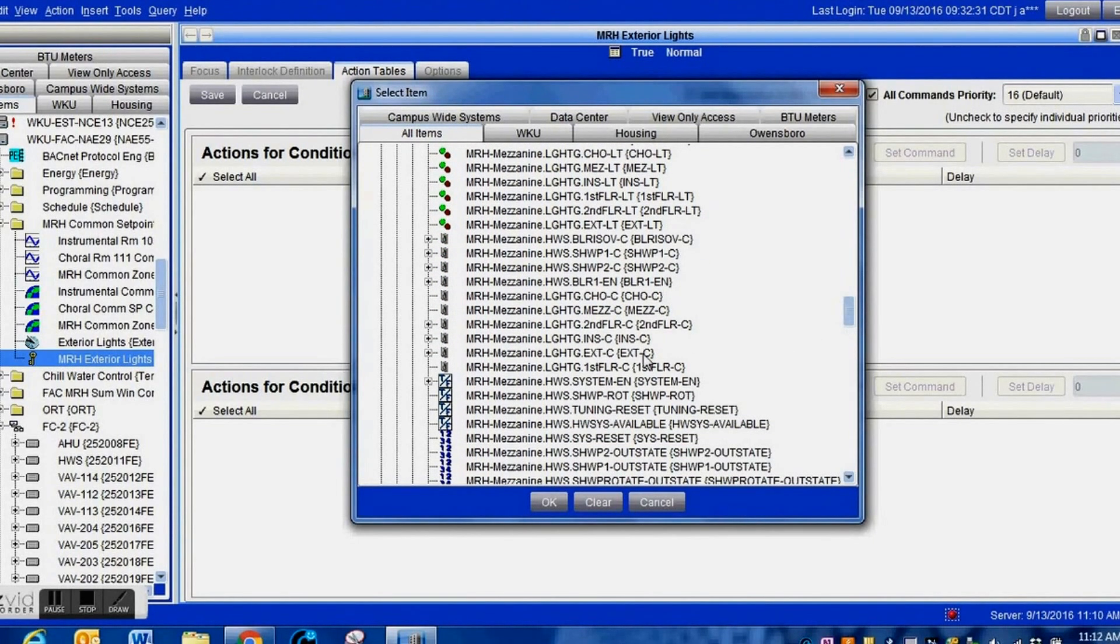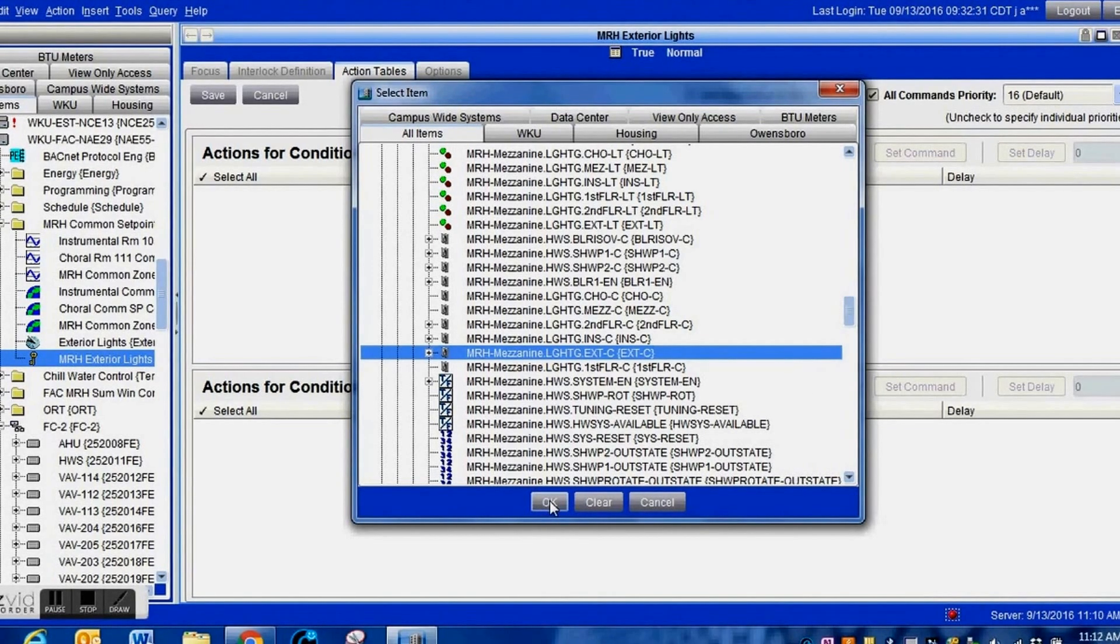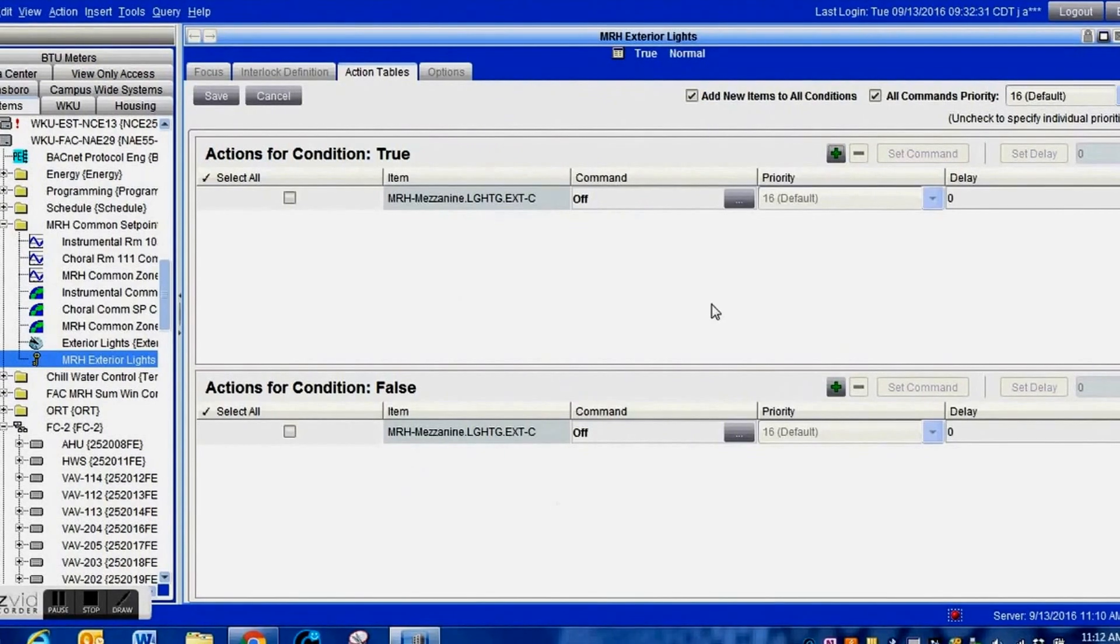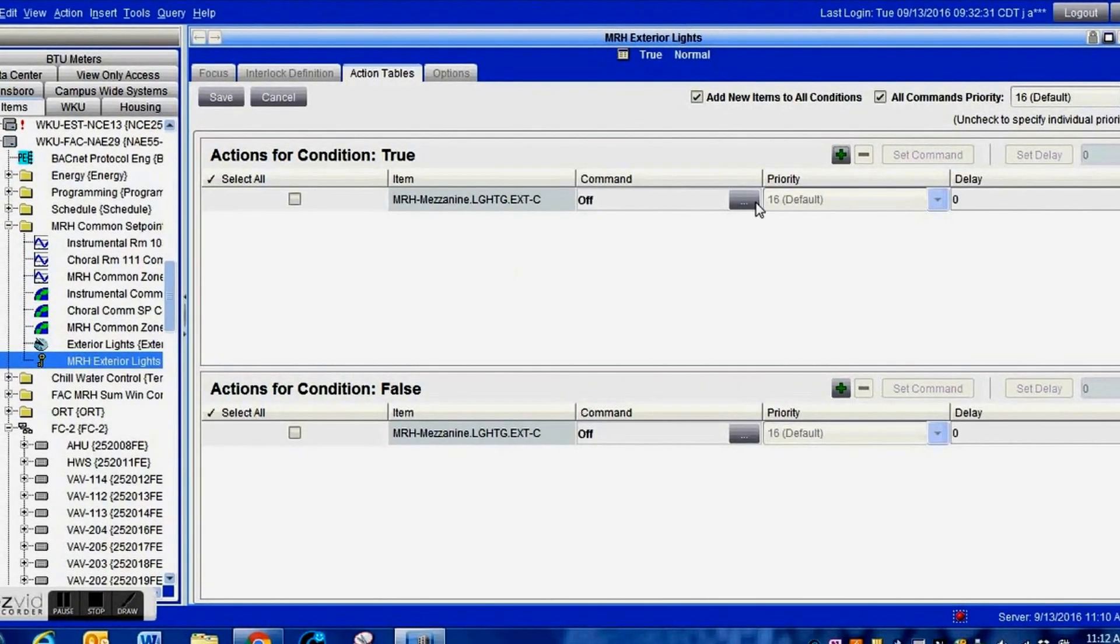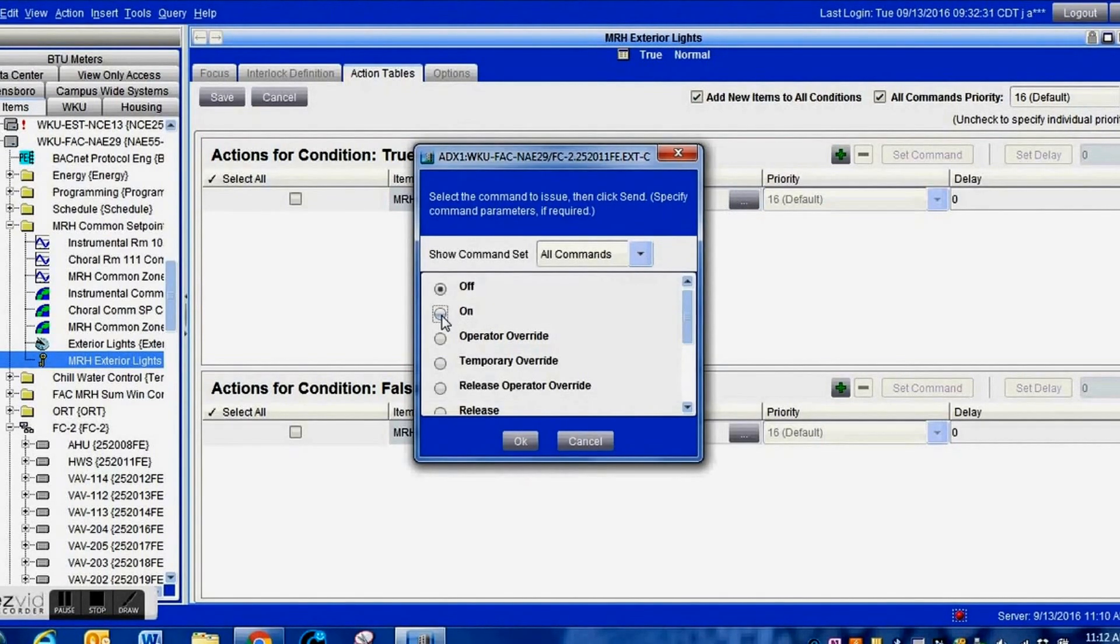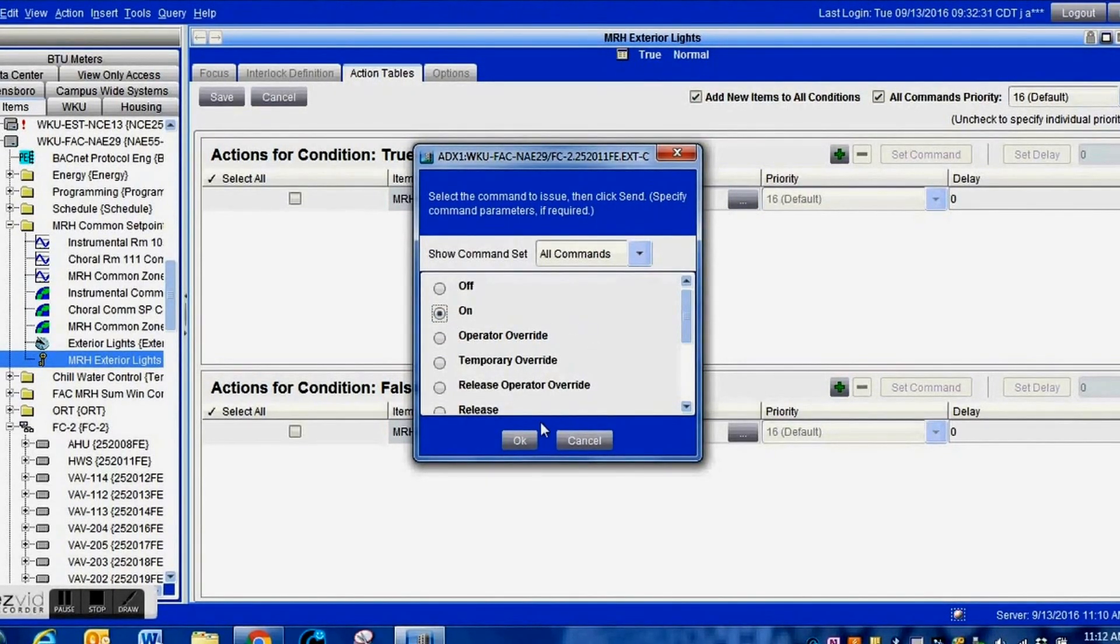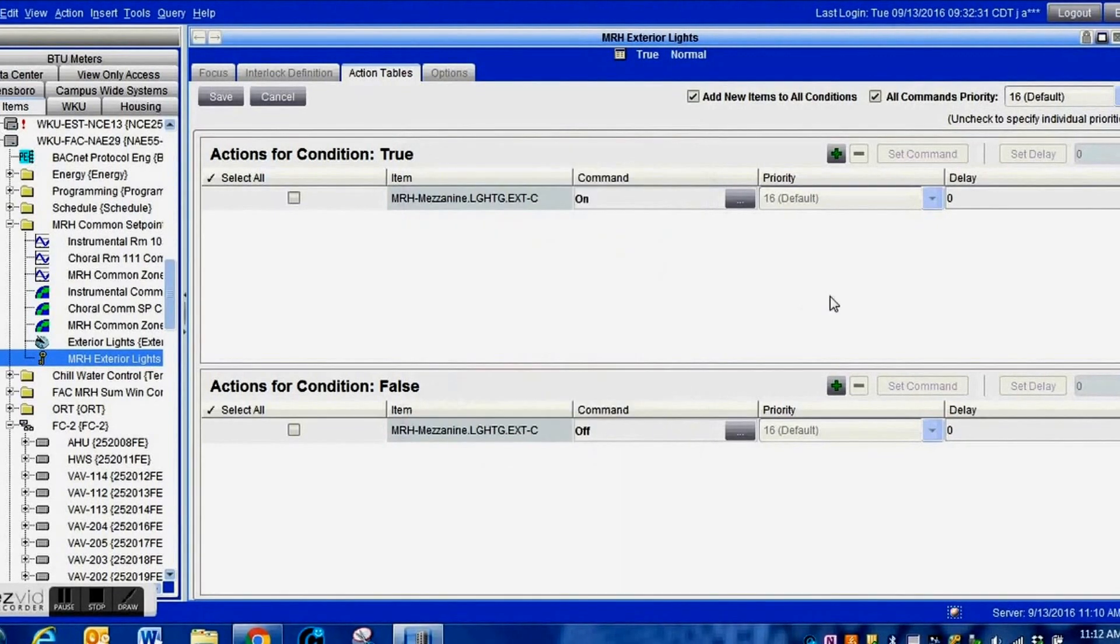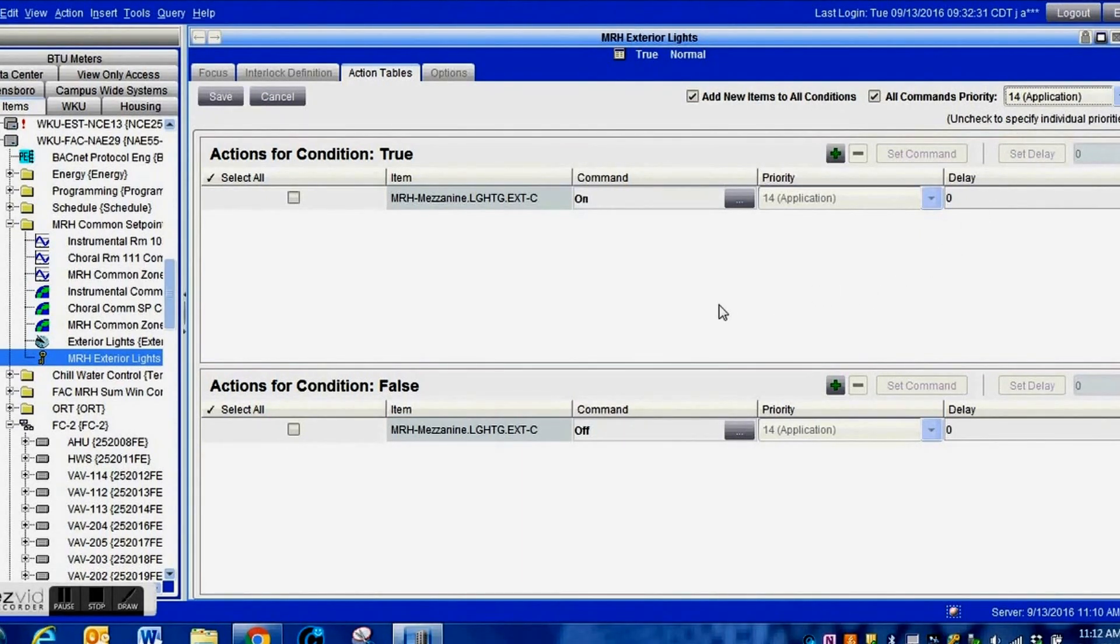Drill down through the system, find the controller where the lights are controlled from, go down to the point, the relay point, the output point in that controller for our exterior lighting. Highlight that, press OK, and this version of Metasys automatically puts one in for true as well as false. I simply go to the true portion. During nighttime I want it to turn that command on.